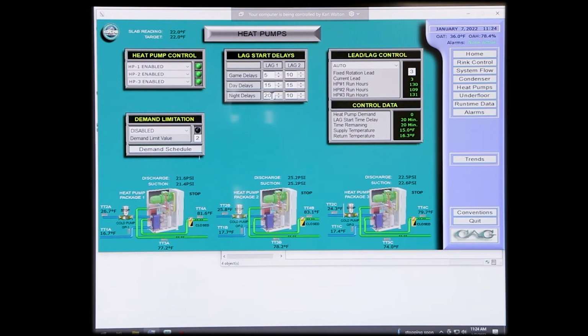There is a limit to how far out you can go. And you'll see that. You can punch in a number like, let's say, 90 minutes, and whether or not the computer will take it, you can actually have that machine wait an hour and a half before it tries to restart. Okay? Oh, no, see, it didn't like it. The max limit is 60, it kicked it back. So you can literally let it wait that long. Which is good, because if it can make set point before it needs that third machine, you don't have to start a whole other machine. Money in the bank.